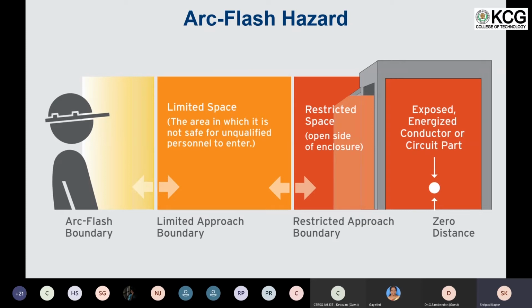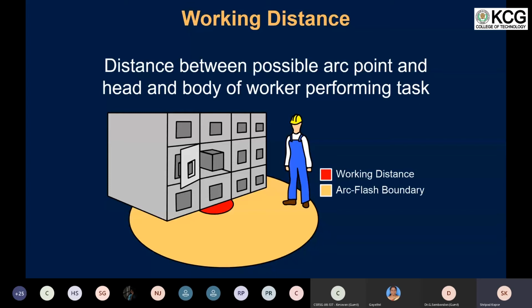So here is an arc flash hazard approach boundary. Here you have zero distance, which is basically the part where the fault is going to occur. It could be a phase-to-phase or phase-to-ground fault, inside the chamber of the switchgear. Then you have the restricted approach boundary, wherein there is a risk of a person getting an electrical shock apart from burn injuries. Then there is the limited approach boundary, where only a qualified person wearing proper personal protective equipment is supposed to enter. Then you have the arc flash boundary, where a person can get a second degree burn. If you wish to visualize, this is the working distance and this is the arc flash boundary.